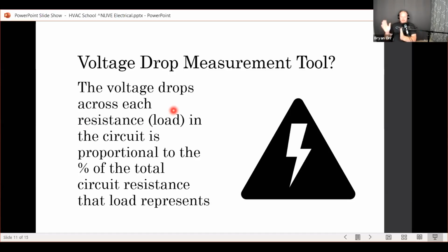Okay, so I've got a circuit, and it's not working right. And I find that I have a bunch of resistance in a loose lug in a disconnect. There's a loose lug in a disconnect, and so it's carboned up, it's been arcing, and so now there's additional resistance in that loose lug, right? We get our heads around that. There's additional resistance. Am I going to measure a voltage drop across that? Well, yeah, I will. Now, it might not be significant, but whatever voltage drop I measure is proportional to the percentage of the total circuit resistance that load represents. So let's take this really simple. If I have an arced up terminal and I measure 24 volts of drop across that arced up terminal on a 240 volt circuit, what does that tell me? That tells me that 10% of the total circuit resistance is in that terminal.